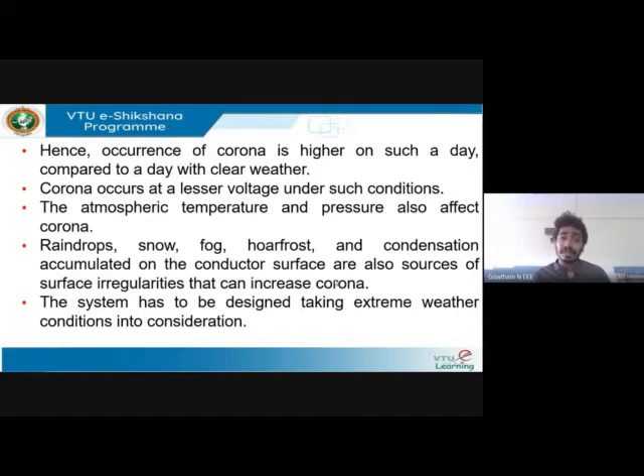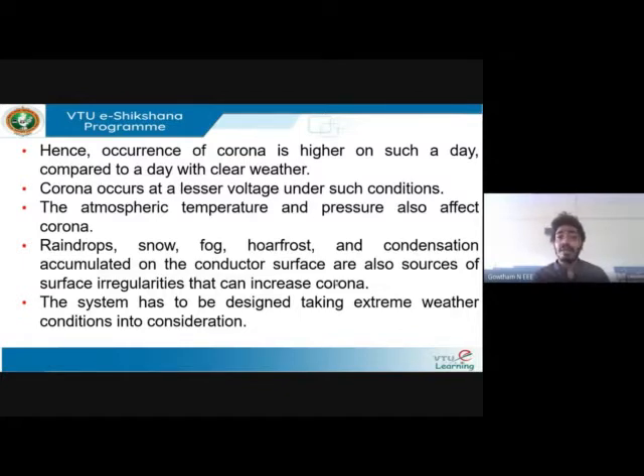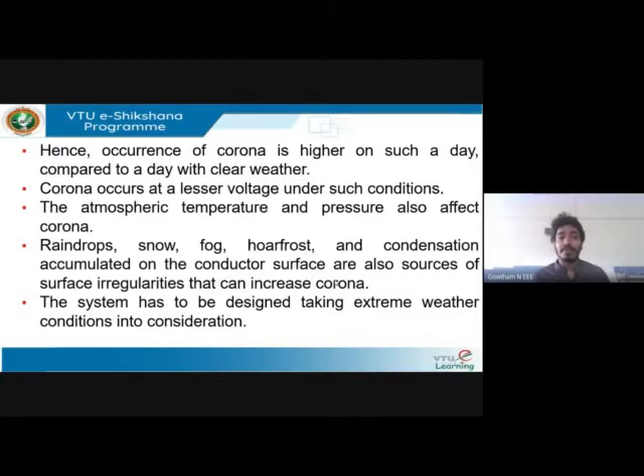If the weather is not clear or is stormy, you can expect corona even at lower voltages — not exactly at 30 kV. Temperature and pressure will obviously affect corona, as will rain drops, snow, fog, frost, and condensation. Surface irregularities in the line — rough surfaces — will also increase corona. All these factors have to be taken into consideration when trying to prevent or reduce corona.